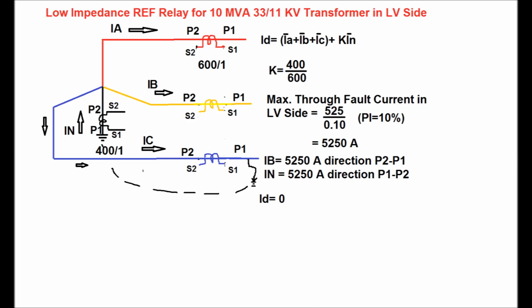The maximum through fault current on the LV side is given by the rated current on the LV side divided by the percentage impedance. Now the percentage impedance is 10%. Considering 10% impedance, the maximum through fault current comes as 5250 ampere. So the primary current that flows in the blue phase is 5250 ampere from direction P2 to P1, but in the case of the NCT, the same current flows, but the direction is from P1 to P2.